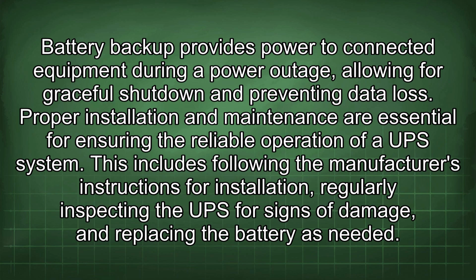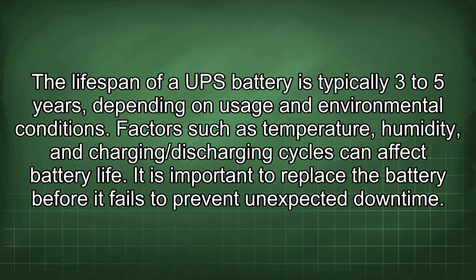Proper installation and maintenance are essential for ensuring the reliable operation of a UPS system. This includes following the manufacturer's instructions for installation, regularly inspecting the UPS for signs of damage, and replacing the battery as needed. The lifespan of a UPS battery is typically 3 to 5 years, depending on usage and environmental conditions. Factors such as temperature, humidity, and charging/discharging cycles can affect battery life. It is important to replace the battery before it fails to prevent unexpected downtime.